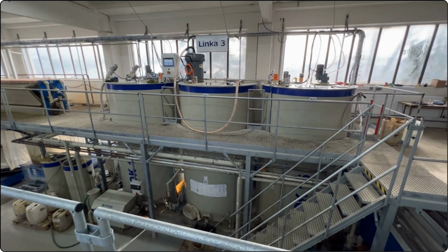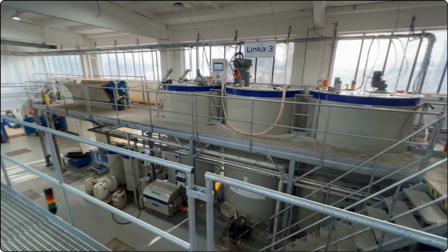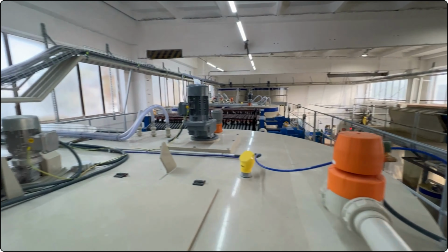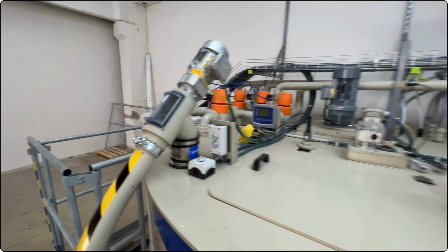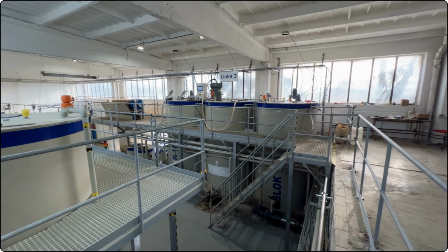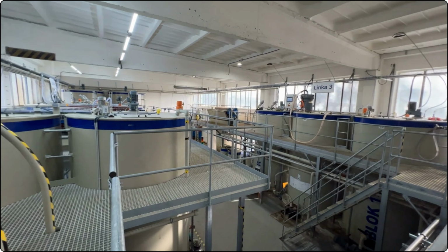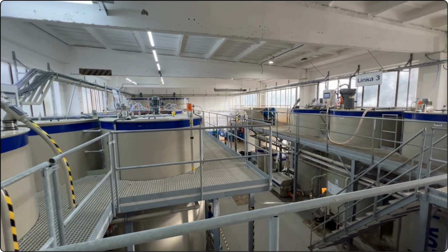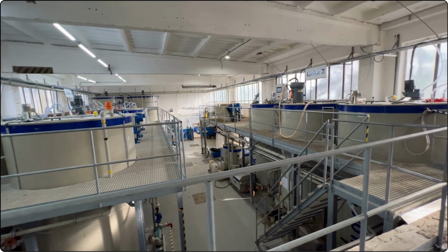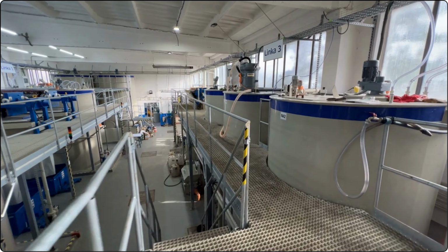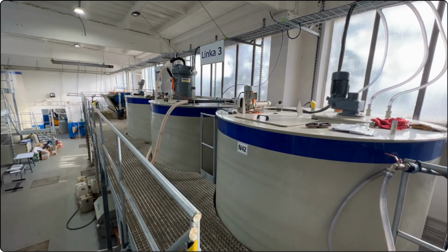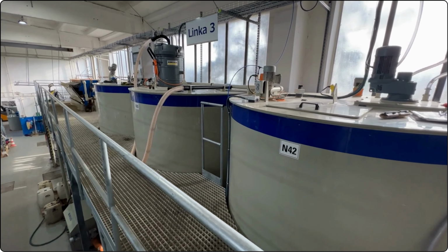The treatment lines work in an automatic batch mode with the possibility of switching to the manual mode, to make adjustments in any step of the ongoing process sequence. Wastewater is pumped from storage tanks to batch reactors where time-segregated processes take place. The reactors are equipped with a vertical agitator, a technological cover, devices for the removal of oil and floating substances, a discharge valve, and ports for the installation of pH measurement and chemical agent dosing fittings.